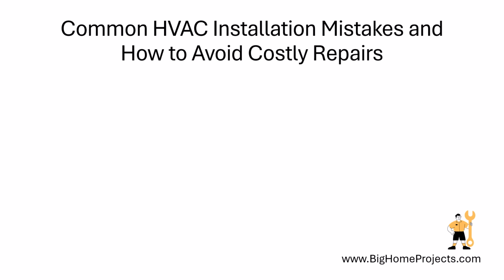Extremely low airflow can signal a blocked filter, undersized ductwork, or a failing blower, so compare comfort across rooms and have airflow checked. People also overlook drainage because the unit still runs, but a missing safety switch can allow a clogged drain to cause expensive water damage, so confirm that the drain and shutoff protection are tested.